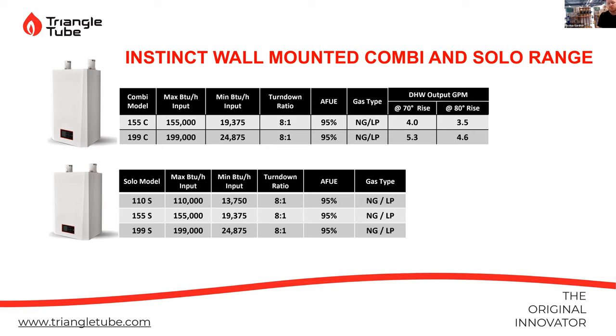One thing with these boilers, we'll go in and we'll look at the controls. We can derate these boilers. So I can actually drop the rating on the heat output at 155 to essentially whatever I want. So if you guys are sizing these units on the domestic load for the combis, we can turn down the CH heating mode and derate these boilers, all right? Those combi boilers come with system pumps already installed. So you'll pipe out of it either going right into your closely spaced tees or your low loss header, depending on what you prefer.